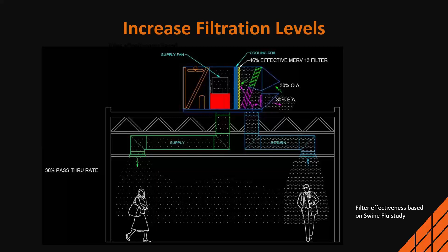Again, if we look at the filtration, we like to reach MERV 13. If we can go a little further, we'll go a little further. Filter costs for a MERV 13 are going to be roughly double the cost of a MERV 8. You're likely going to have to change that filter more often. Because it's a better filter, it's capturing more items, it's going to load up sooner. Likely somewhere about twice as often, but what we recommend is once a month you go up and check, once you put the new filters in. You don't need to replace them once a month. You need to go check them and then figure out what your new schedule is. Just replacing them is just spending money. If they're not loaded up, you don't need to replace them yet.